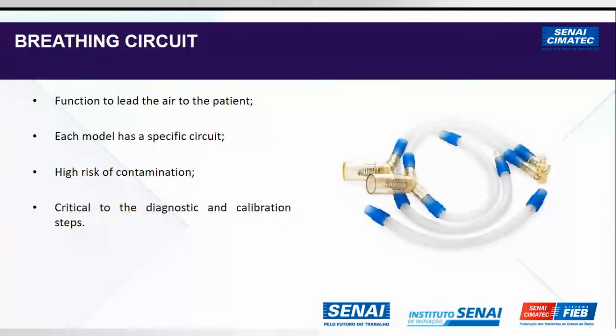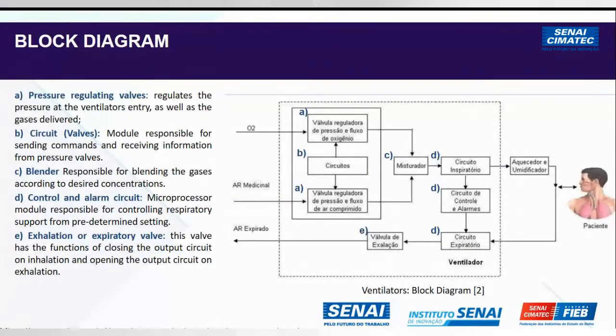The exhalation or expiratory valve. Oh, come back, please. The exhalation or expiratory valve has the function of closing the output circuit of inhalation and opening the output circuit of exhalation. It is important to say that exhalation is very dangerous for the team because the aerosols of the patients can be contaminated with COVID or another virus, another disease, and you need to put a HEPA filter in the valve, on the patient side or before the exhalation valve, to clean the equipment. It's very important to use protective equipment for the whole team in the ICU. Next, please.